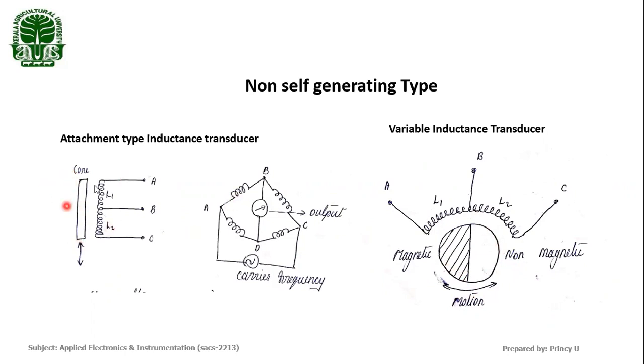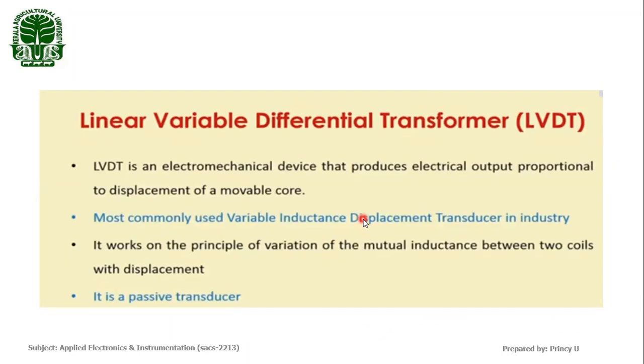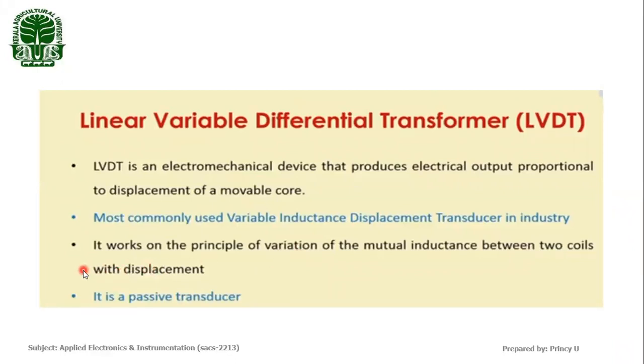This is the same as the attachment type, but here we can measure angular motion. Another important one is the Linear Variable Differential Transformer — LVDT. It is an inductive-type transducer, an electromechanical device that produces an electrical output proportional to the displacement of a movable core. The most commonly used variable inductance transducer in industry is the LVDT, and it works on the principle of variation of mutual inductance between two coils with displacement.